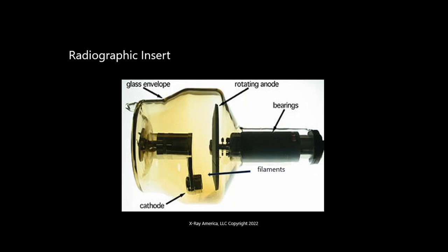So you have a cathode head, and then you have filaments. You have an electrical field. On the cathode side, you have up to negative 75 kV, or 75,000 volts. At the anode end, you have positive 75 kV. What that creates is a tremendous energy potential. This is where the action is. This is why you need a vacuum in here, so that that energy potential can be controlled.